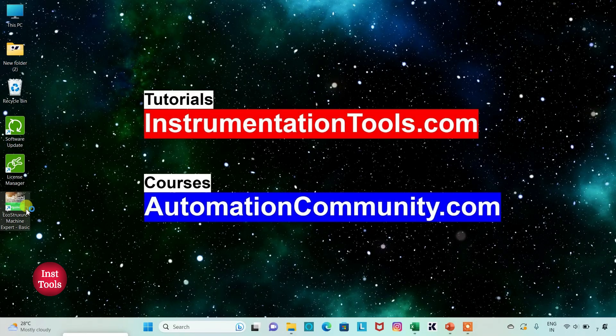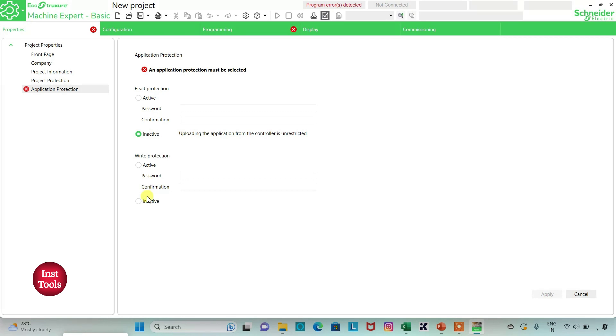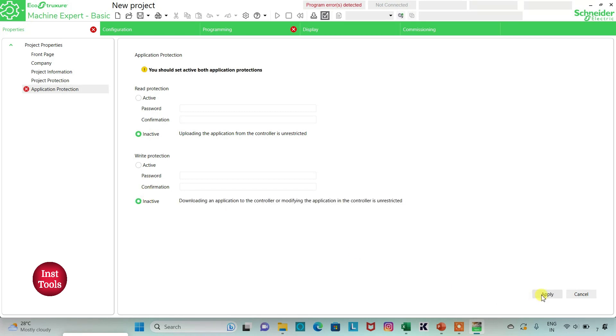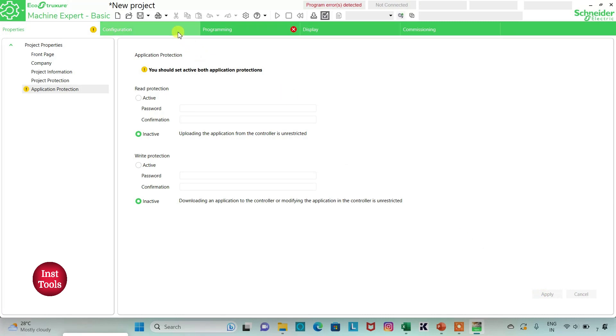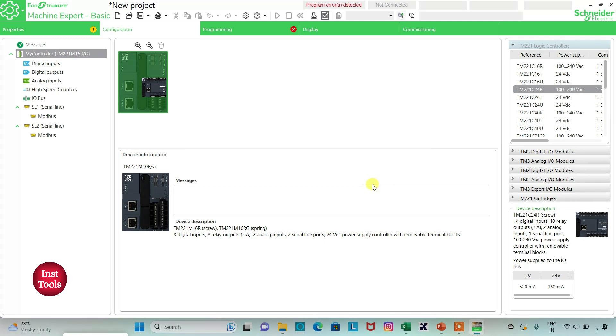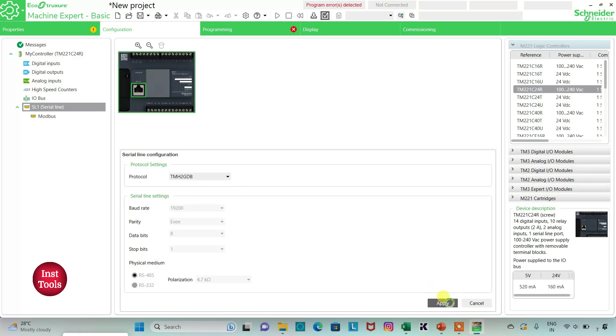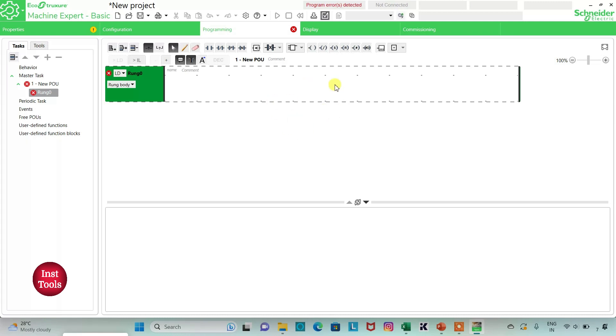I will open EcoStruxure Machine Expert Basic. I will keep read protection as inactive and write protection as inactive, and then click on Apply. I will go to the Configuration tab — here is a list of different logic controllers. I will be using TM221 C24R. I will also go to Serial Line, select the protocol as TMH2GDB, and then click Apply. Then I will go to the Programming tab where I will be drawing the ladder diagram for the Boolean expression.